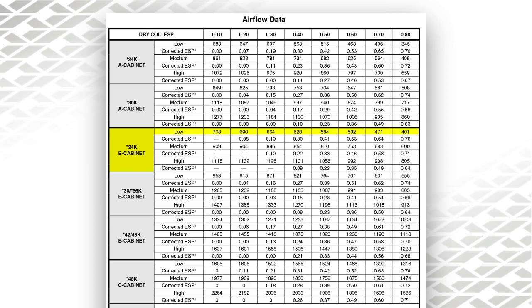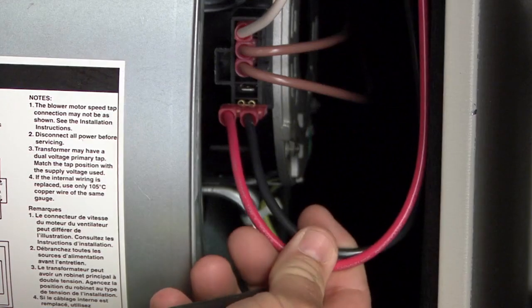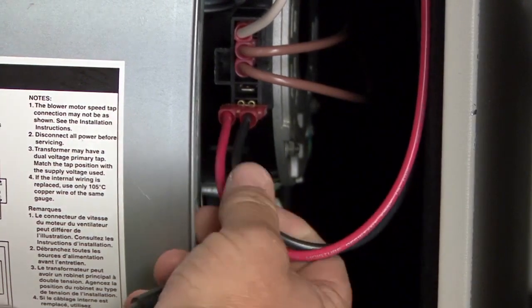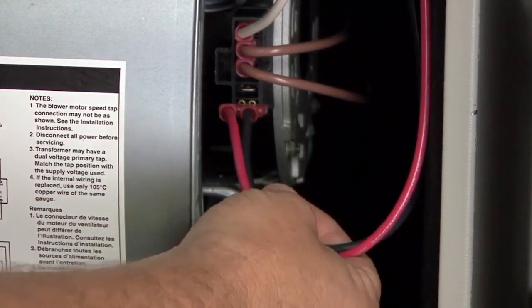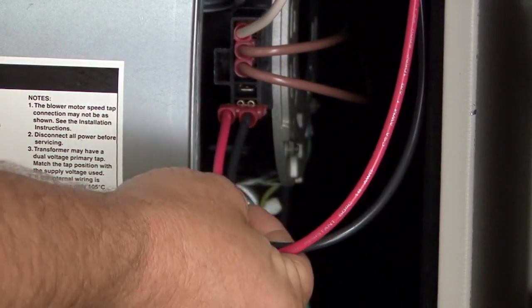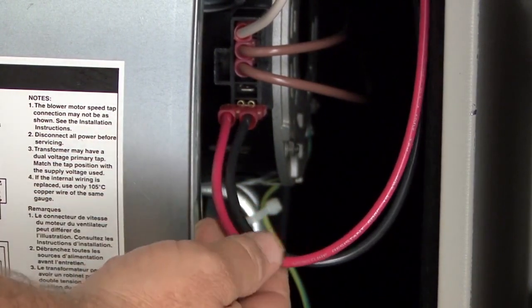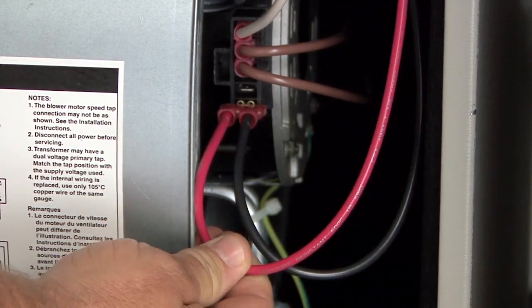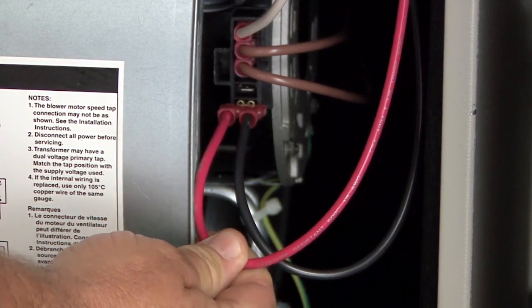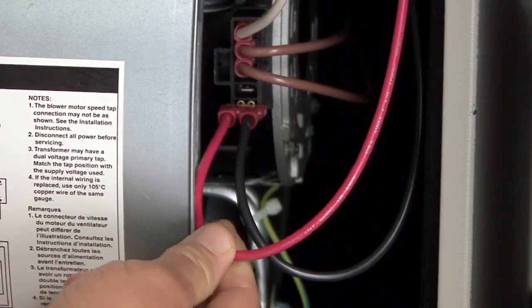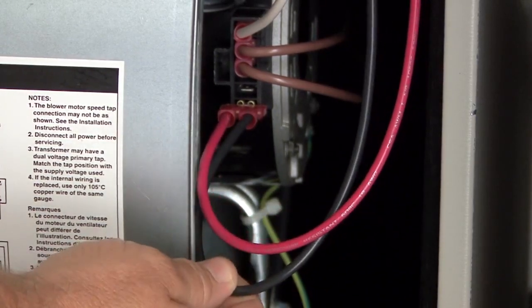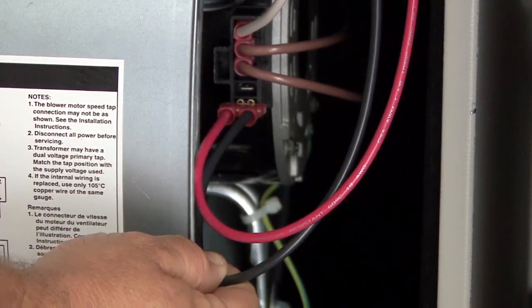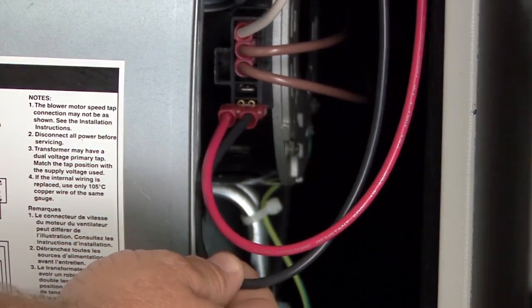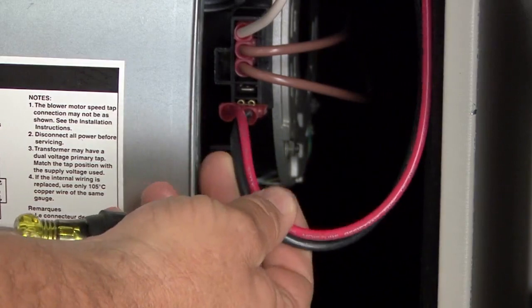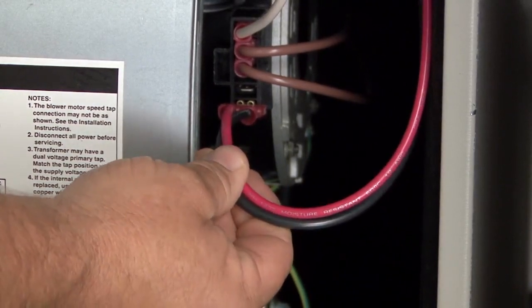So how do you make that speed adjustment? That's what I want to talk about real quick. So the red and black wires coming down to this blower assembly go to a double spade terminal and plug on to number 6 terminal of that motor. Red is your heat speed, electric heat speed, not heat pump heating speed, electric heat speed. Black would be your cooling or heat pump airflow speed. So right now they're both going and energizing the same speed on the motor.